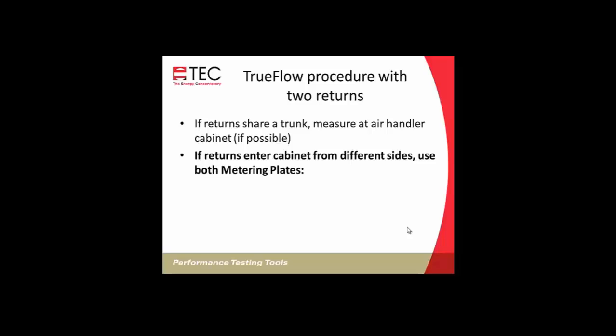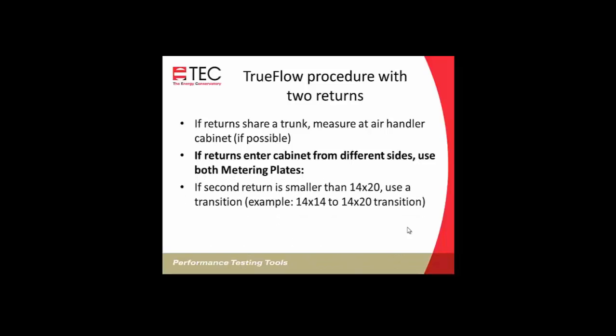Sometimes returns will enter a cabinet from different sides, and if the second return is smaller than 14 by 20, you can use a transition. For example, if you commonly run across something like a second return that's a 14 by 14, you can fabricate a 14 by 14 to 14 by 20 transition, and then put the 14 by 20 plate at the end of that transition. And that way, all the airflow is moving across that TrueFlow, and you can get a measurement on that second return that way.